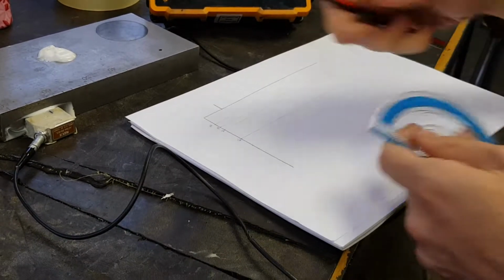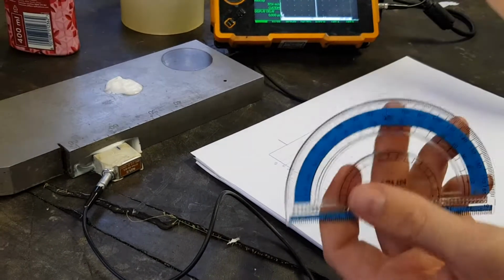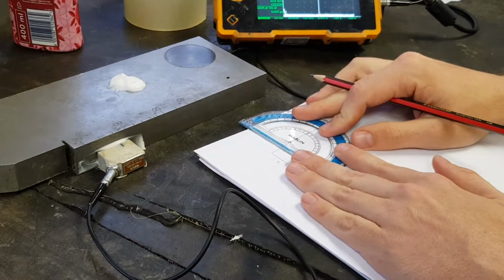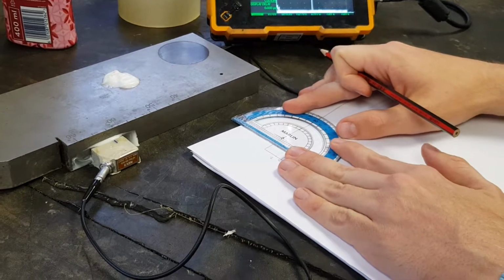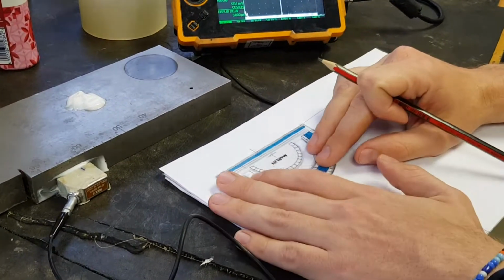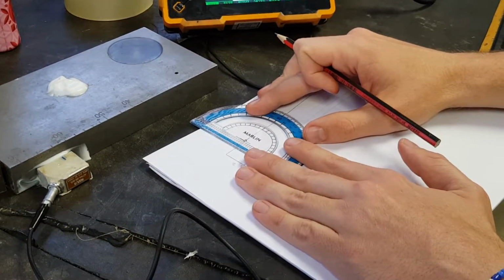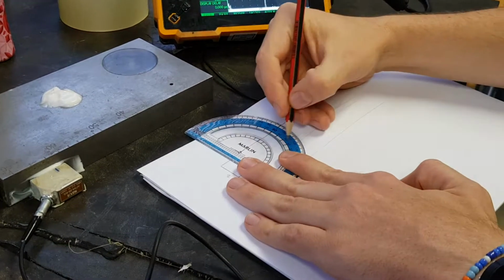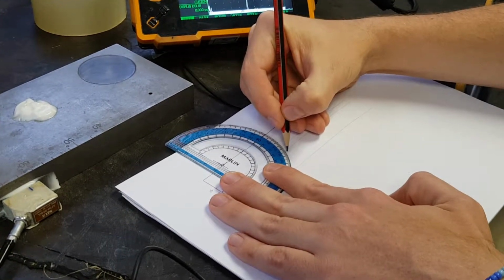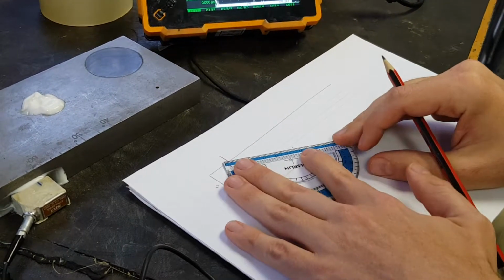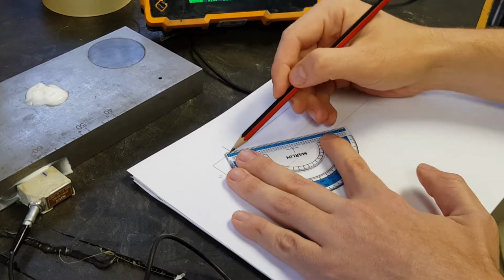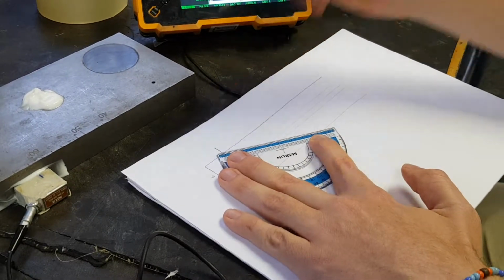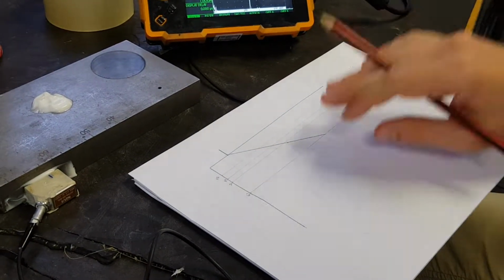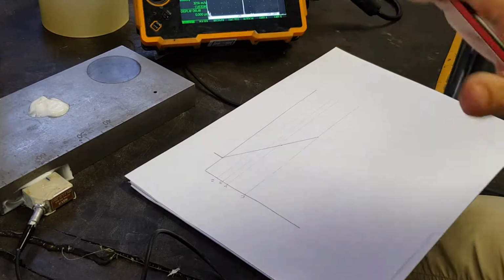So what I'll do then, I just mark the probe beam origin here somewhere. It doesn't matter where you mark it, you just mark it. Always put your protractor down like this, never like this in ultrasonic testing. Make sure it's aligned properly, and there where the number 60 is, remember my beam angle was 61, so I'll just draw in a beam at 61 degrees. Fairly simple. That should be my 100% isobar of my beam.